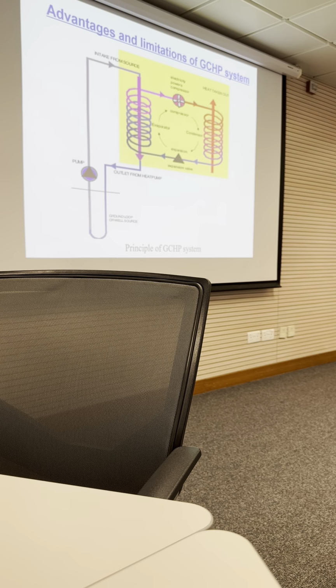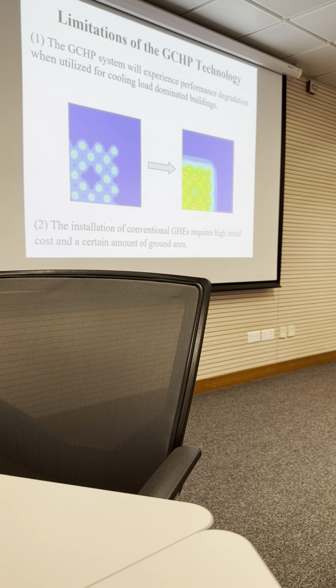The ground coupled heat pump system will experience performance degradation when utilized for cooling load-dominated buildings. For example, these are the boreholes. Then, gradually, we inject energy into the ground. We use the word inject, not reject. Inject energy into the ground. Gradually, you can see the temperature is higher and higher. We know the efficiency, the COP of the heat pump air conditioning system, in fact, is significantly affected by the temperature. So if this temperature is higher, the COP is lower.